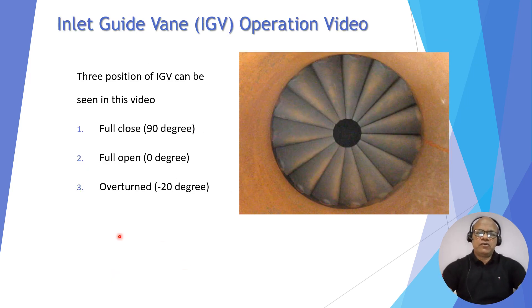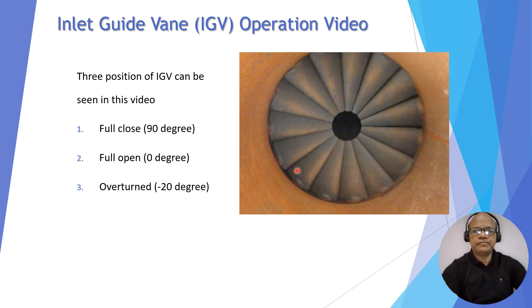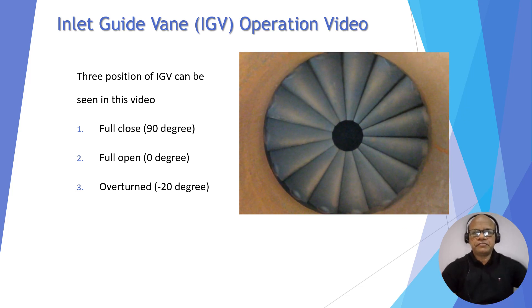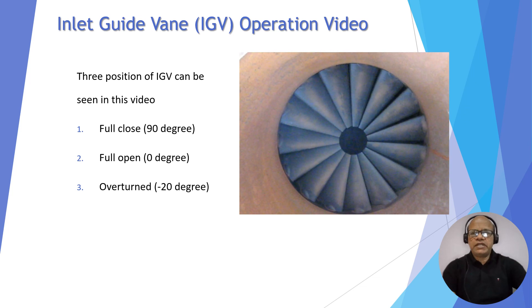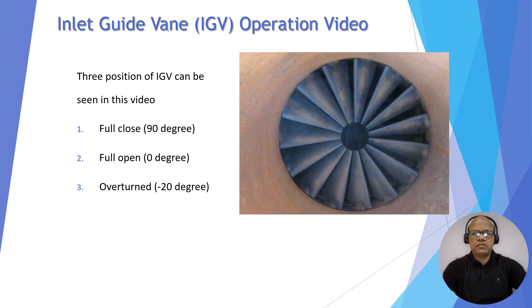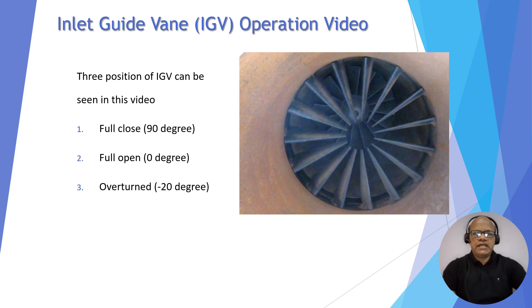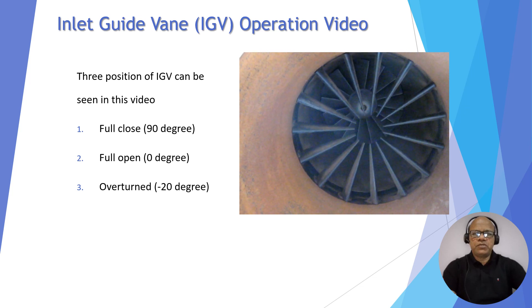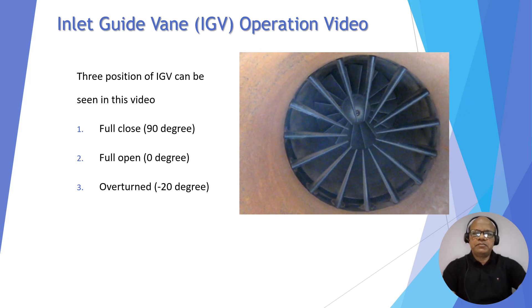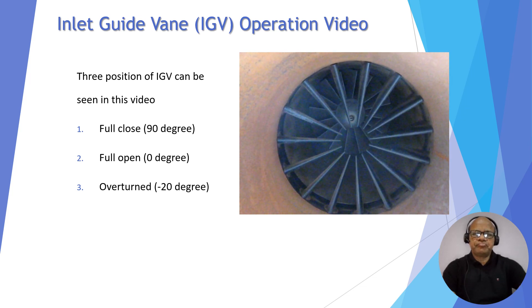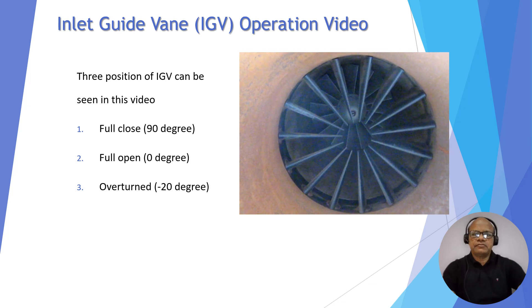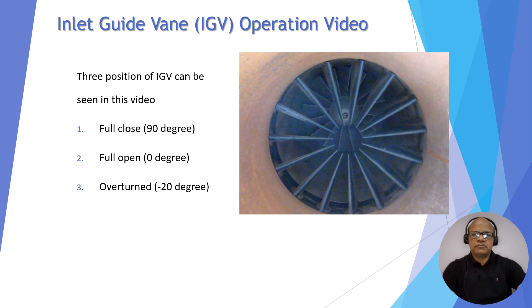Now you will see the actual video of the operation of IGV. Full close is 90 degrees, full open is 0 degrees, and overturned is minus 20 degrees. This is the full close position. Now it starts opening from 90 degrees. It is opening. Now it is fully axial — this is the fully axial, full open position at 0 degrees. Now it is moving towards the overturn position at minus 20 degrees.